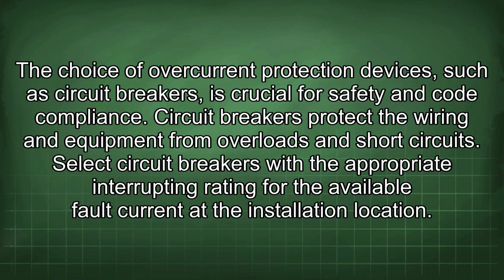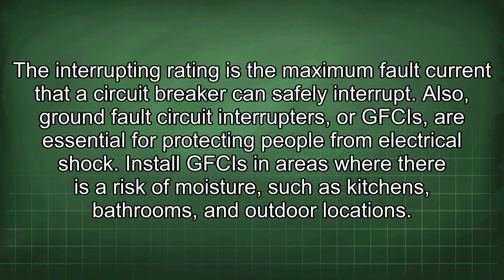The choice of overcurrent protection devices, such as circuit breakers, is crucial for safety and code compliance. Circuit breakers protect the wiring and equipment from overloads and short circuits. Select circuit breakers with the appropriate interrupting rating for the available fault current at the installation location. The interrupting rating is the maximum fault current that a circuit breaker can safely interrupt. Also, ground fault circuit interrupters, or GFCIs, are essential for protecting people from electrical shock. Install GFCIs in areas where there is a risk of moisture, such as kitchens, bathrooms, and outdoor locations.